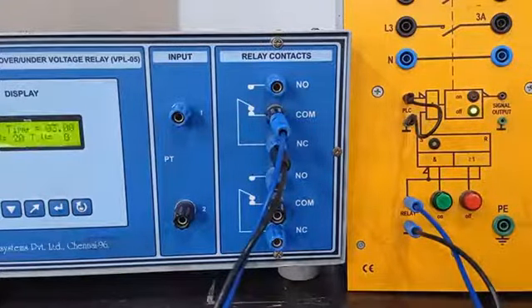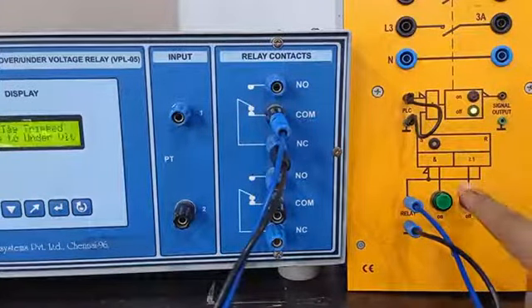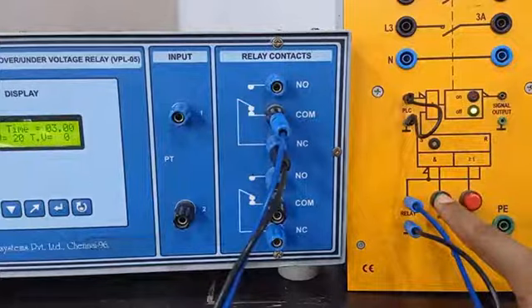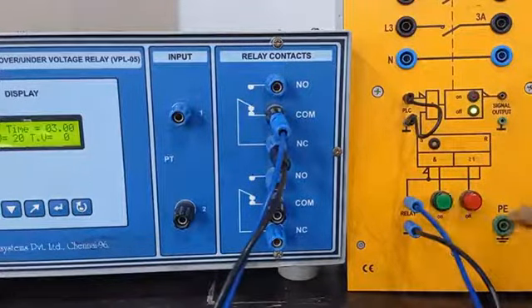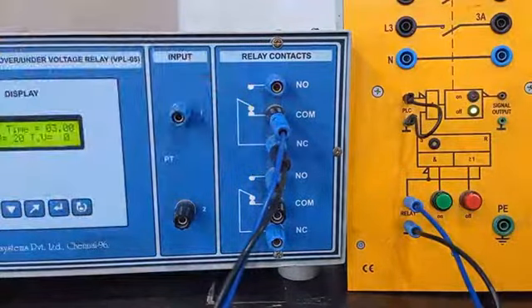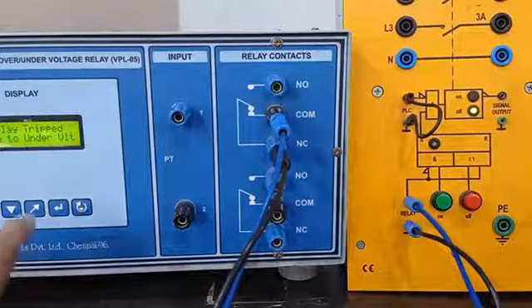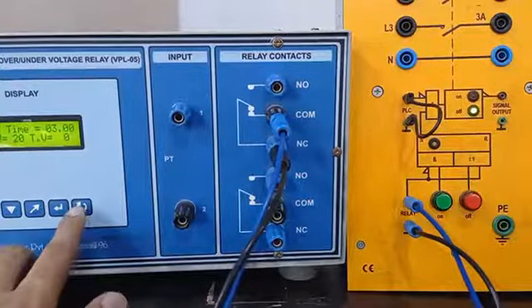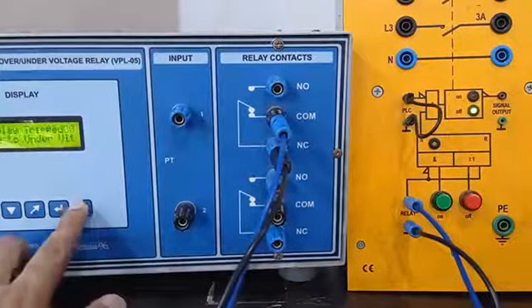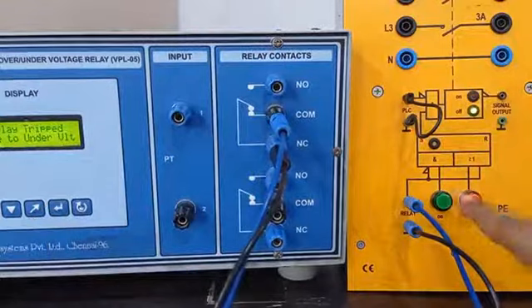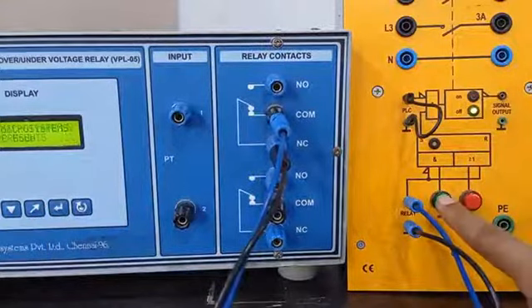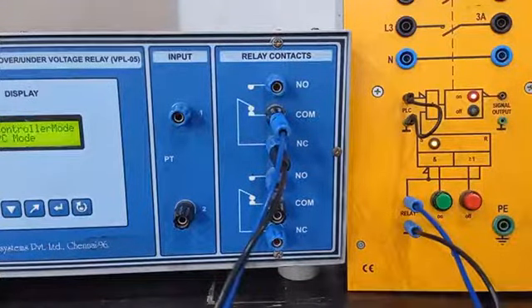Now in this condition, if I try to close the circuit breaker by pressing the ON button, I would not be able to do that. Reason: the relay has tripped and there is a transition of its contacts. In order to re-close the circuit breaker, I will have to reset the relay. Here I am going to reset the relay. Relay has been reset. Now if I press the ON button, the circuit breaker is closed.